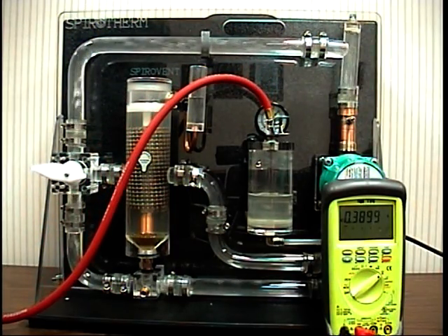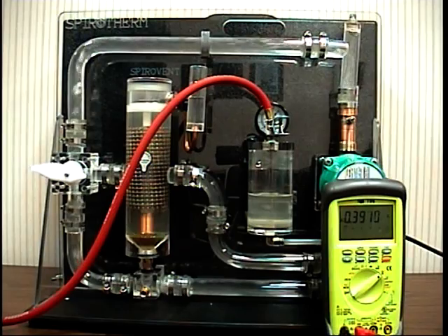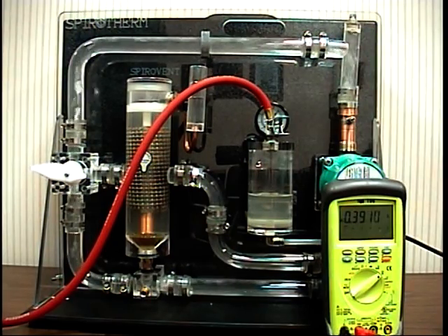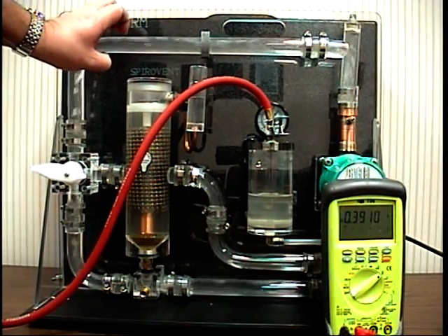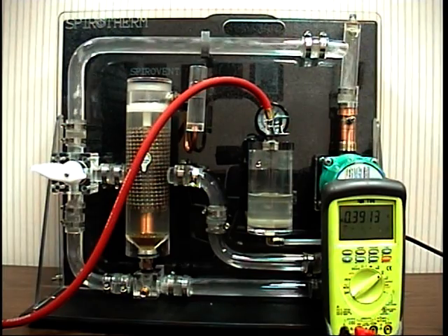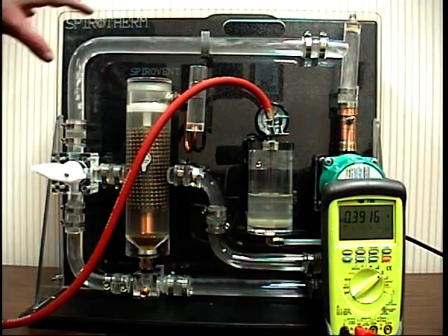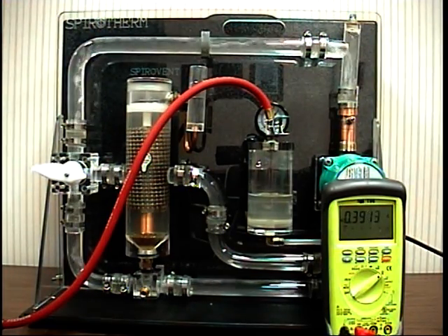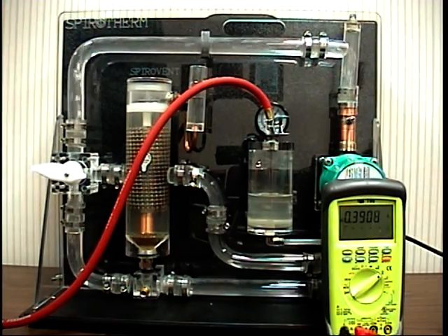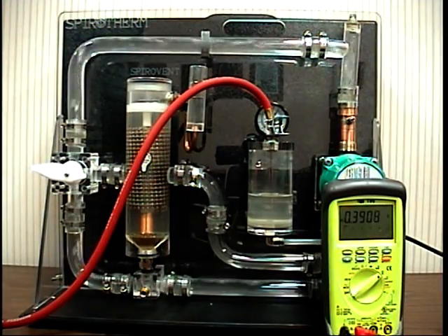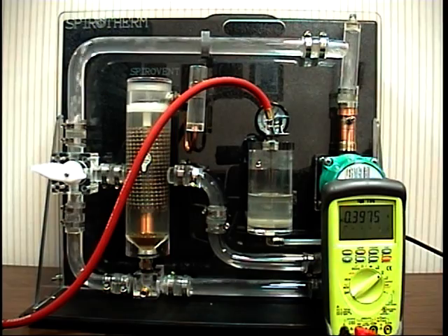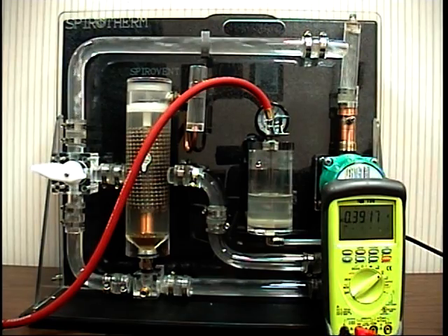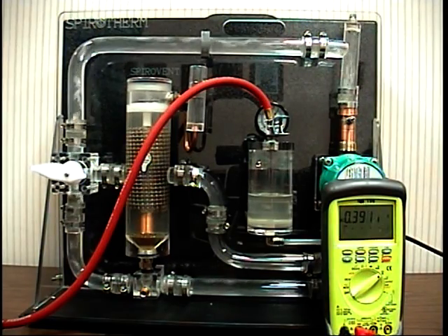All of a sudden, without eliminating the air out of the system, we've increased the velocity of water because we're compressing the air bubbles within the system, therefore creating a little bit more flow. Still, all the air is still there at this point in time. So increasing your pressure in the system will definitely increase your system flow because you're compressing those air bubbles, but they're still there.